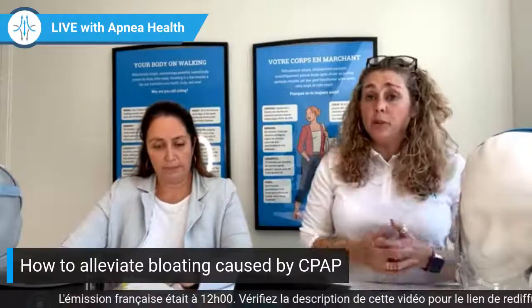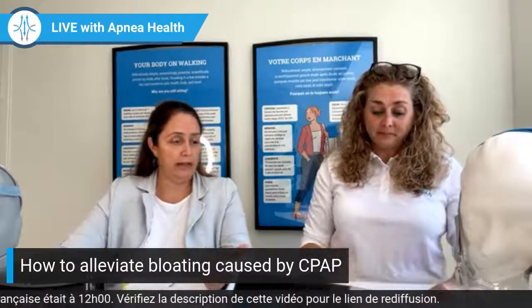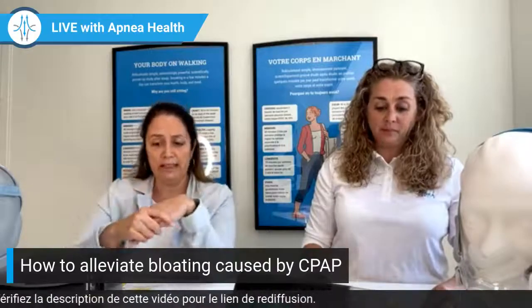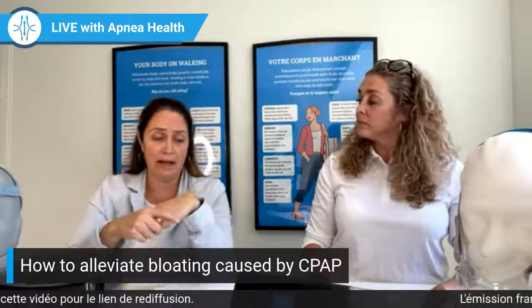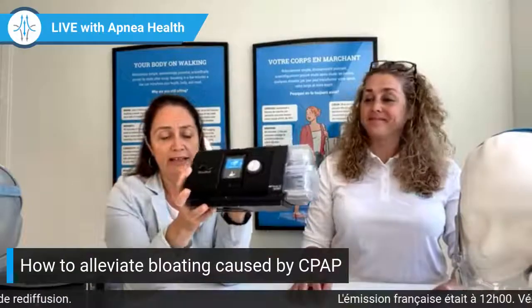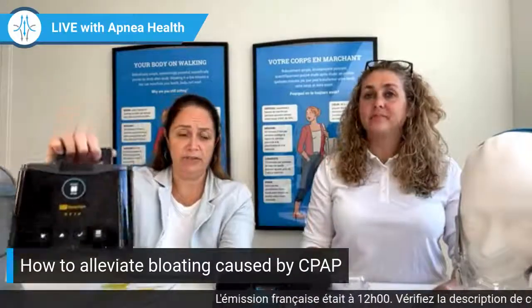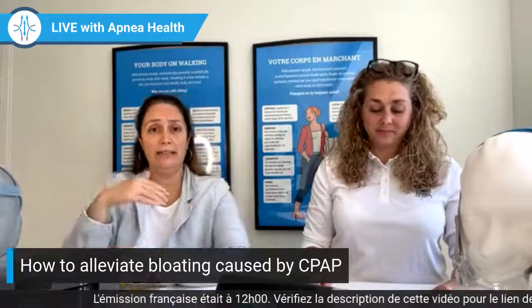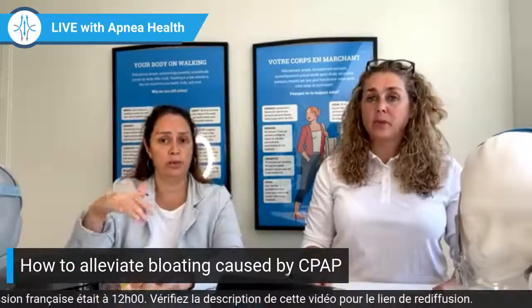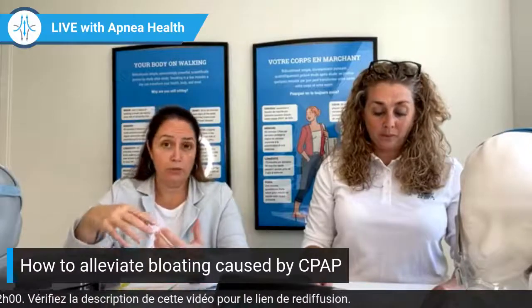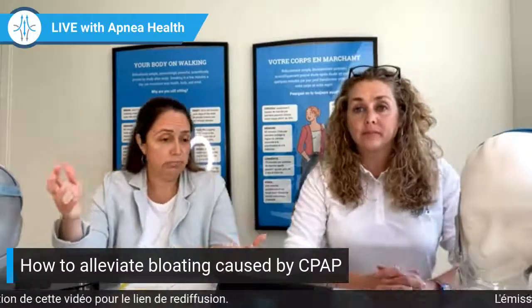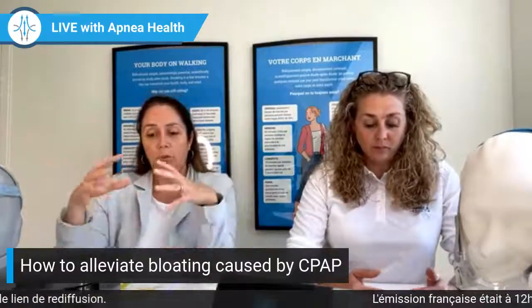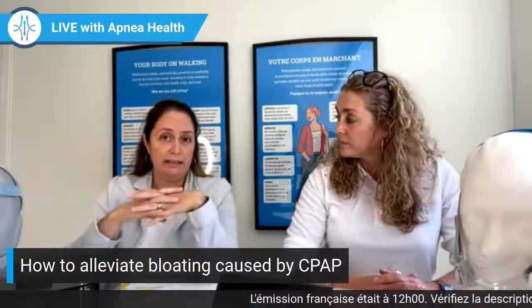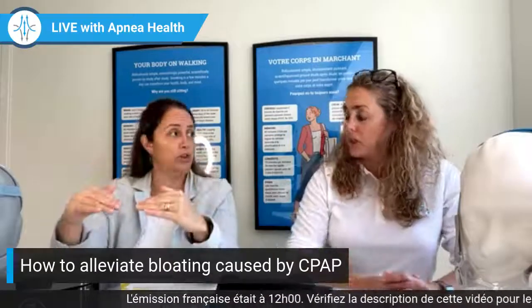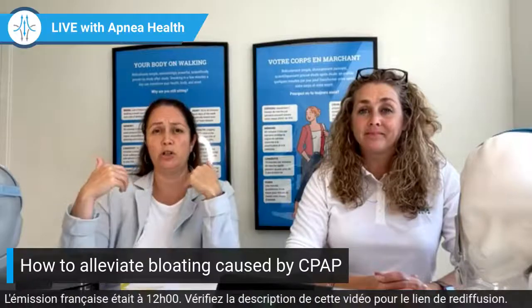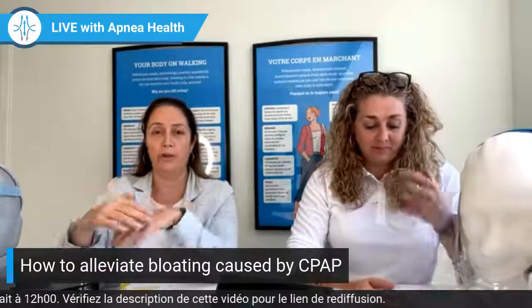So what about solution number 2? We were talking about the exhaling problem. Yep. With the new devices, they all have that now, like the S10 from ResMed and the same thing with the SleepStyle from Fisher & Paykel. There's what we call the EPR, for expiratory pressure relief. So how does it work? When you exhale, the machine will detect that you're doing it and will lower the pressure. So you won't feel as much resistance when you're breathing out.